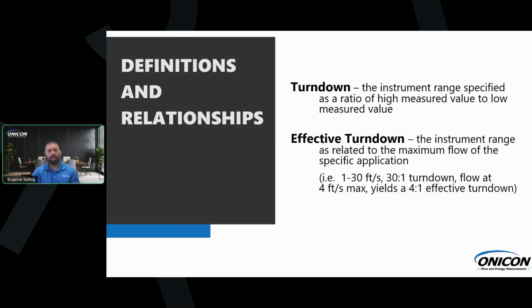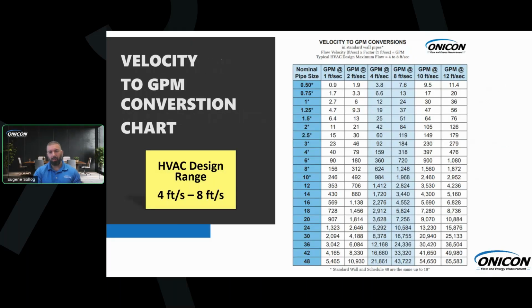And to look at turn down. Every flow meter is going to have a specific turn down, right? So this one is up to 33 feet per second, from just about 1 foot per second to 33 feet per second. That's all well and good, except for our industry in HVAC, we are going to be looking at the effective turn down. So that's what we find important.